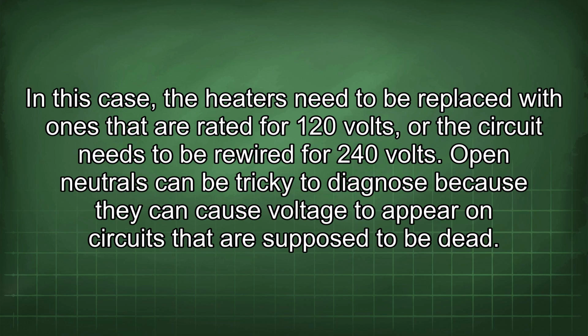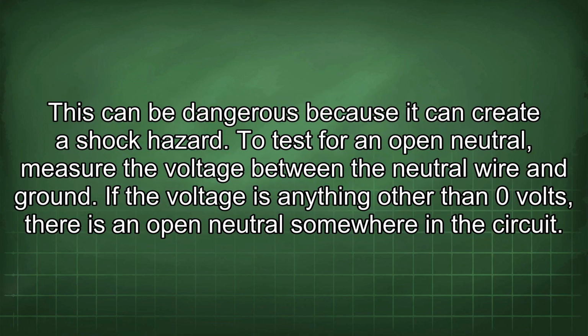Open neutrals can be tricky to diagnose because they can cause voltage to appear on the circuits that are supposed to be dead. This can be dangerous because it can create a shock hazard. To test for an open neutral, measure the voltage between the neutral wire and ground.